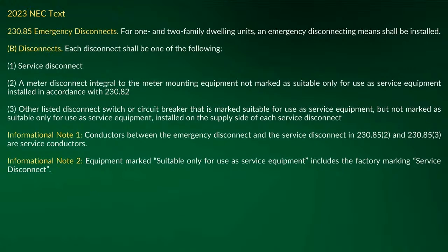In that case, what I would say is you still leave that as your first point of disconnect, and then you just run a supplemental electrode for your bonding of your transfer equipment. And I think that's allowed per 250.24. I believe it was 250.24.